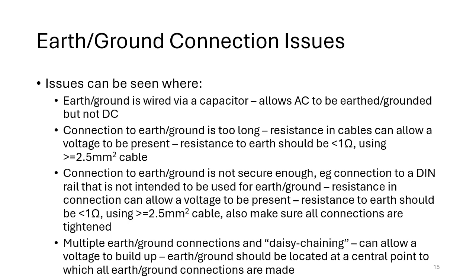Finally, you need to make sure about multiple earth and ground connections and daisy chaining. Again, that can allow a build-up of voltage. If you've got one earth in one panel going to another earth in another panel, goes to another earth in another panel, then that can ultimately end up in a higher than 1 ohm resistance, and also if you've got your cable resistance as well, that can build up to a high voltage. So ideally your earth or ground should be located at a single central point, and all your earth or ground connections should be made directly to that. You shouldn't be doing daisy chaining, and you need to make sure also that that earth or ground connection is near enough as well. Otherwise you may need specific additional earth or ground connections.